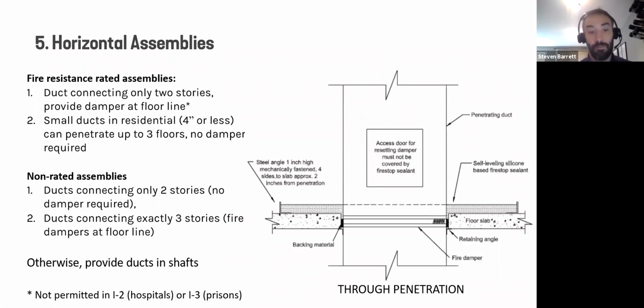Some buildings, though, have non-rated floor assemblies based on their construction type. So in those cases, you're permitted by code to connect 2 stories without having any damper, or to connect 3 stories, but no more than 3, with fire dampers at each floor line. If you don't meet any of these requirements, you must run your duct in a shaft. That's why I said earlier, basically you should always be running your ducts in shafts, but there are some specific allowances in code to run a duct through a floor, and possibly with a fire damper at the floor line, depending on whether or not the floor assembly is fire resistance rated. And at the bottom there, I note that I2 and I3, which are hospitals and prisons, these aren't permitted.